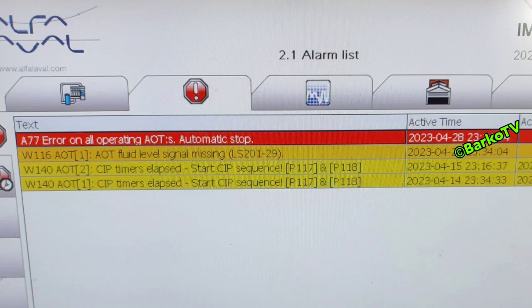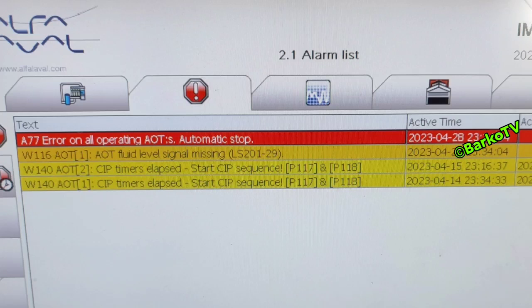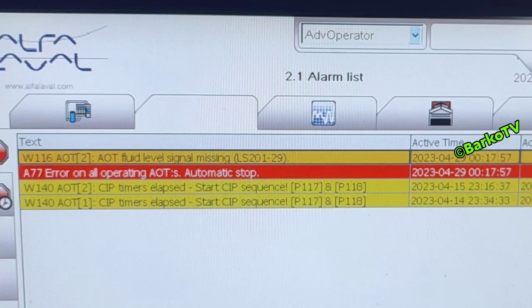A 77 error on all operating AOT — automatic stop on both AOT. The alarm is AOT fluid level signal missing: LS 201-29, that is the level transmitter AOT 1. We try again on system 2 AOT fluid signal — same, it's level missing at the level transmitter.